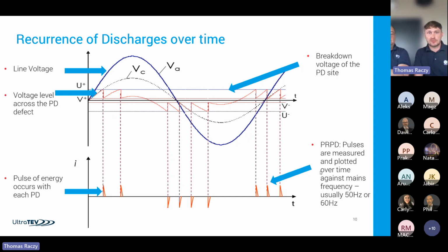That voltage across the cavity will be much lower than the voltage across the healthy insulation. Obviously, the cavity is now filled with air as opposed to insulation, and that air has every chance to break down once the sufficient voltage is reached. And that voltage is highlighted in that graph as U positive, so the PD inception voltage. So the voltage at which we reach high enough volts to drive that spark, PD spark across the gap, and you can see those pulses.